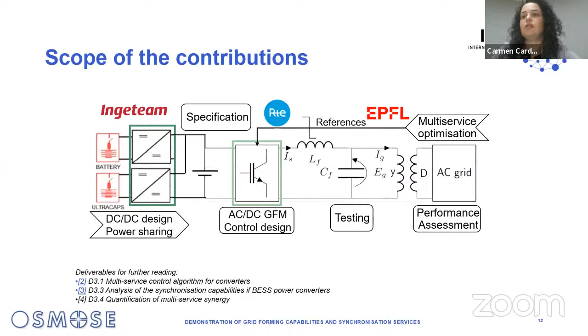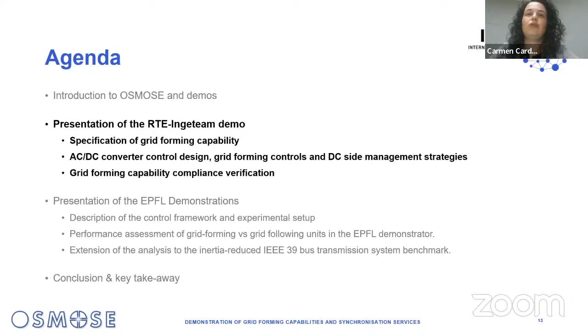And now I would like to focus, in this first part of the presentation, on the contribution that we bring with Ingeteam while working in RTE. So this is quite a technical part, so I will try to stay clear for everyone. Basically the challenge, as I said, is defining what grid forming capability is, in a way that is suited for an industrial environment, so that TSOs can get the performance they're expecting, and at the same time manufacturers are able to develop technological solutions. And in this work, we propose this definition: a grid forming unit shall, within its rated power and current, be capable of self-synchronizing, standalone, and provide synchronization services.